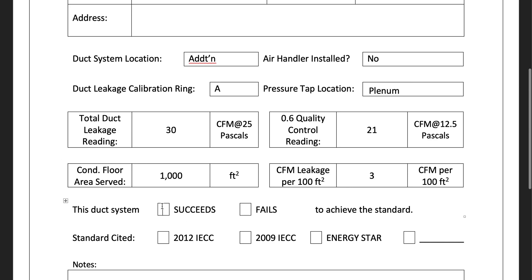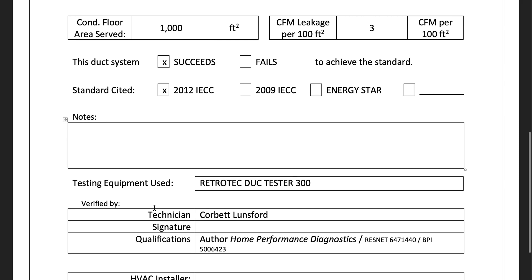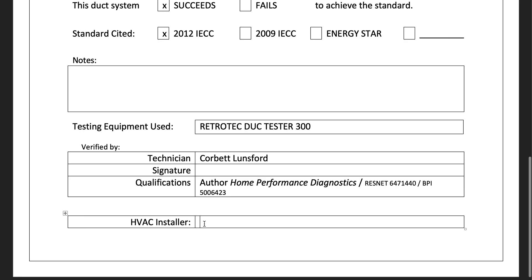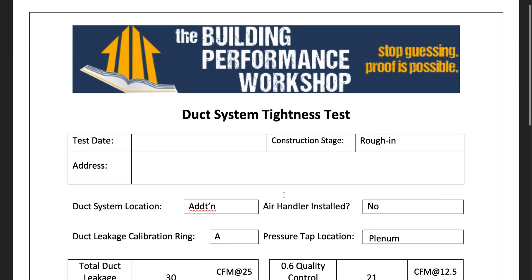The 0.6 quality control reading for the duct test: same as the other report — you want this to be roughly two-thirds of your main reading. You actually test it: run the CFM at 12.5 pascals, which is half of 25, and the flow should cut by a third. Conditioned floor area served, CFM leakage per 100 square feet is 3, and we succeed. Include any notes, the test equipment used, the technician name, signature, qualifications, and the HVAC installer you were working with. This is a comprehensive report that makes you look very professional. If you want more reporting software, check out APT Reports, my training portal, and the YouTube channel and TV show Home Diagnosis — all links are at buildingperformanceworkshop.com.